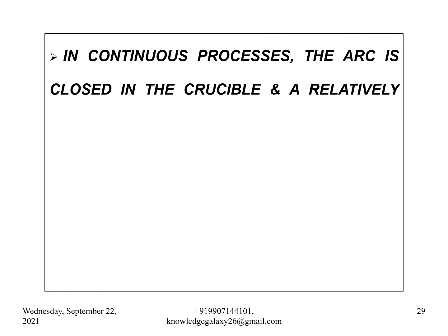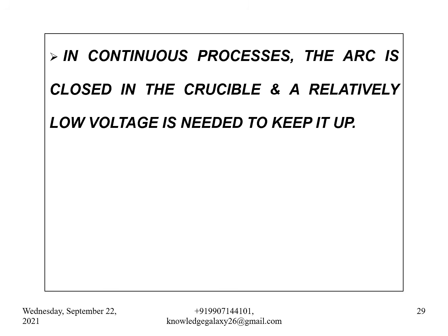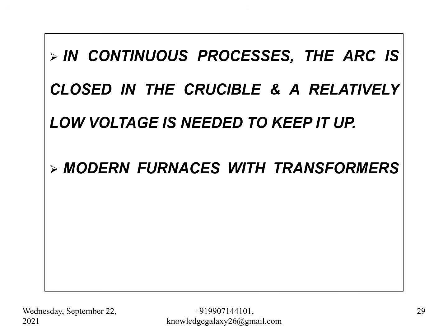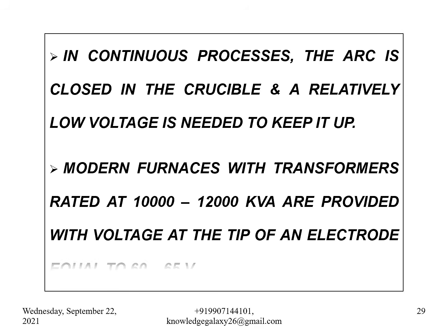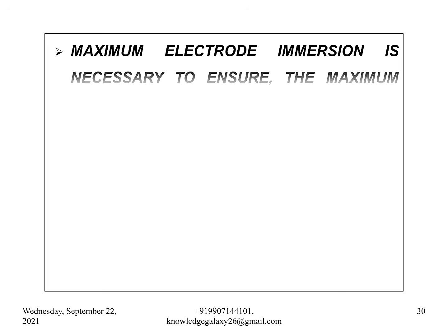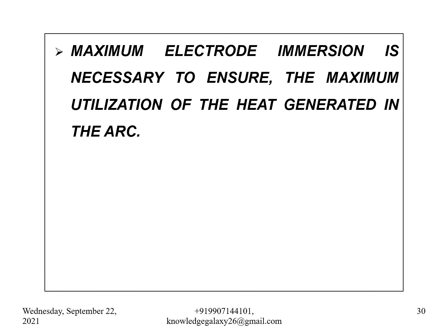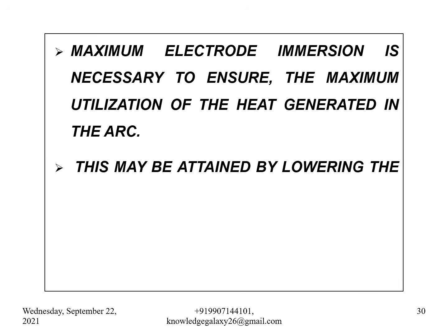In continuous processes, the arc is closed in the crucible and a relatively low voltage is needed to keep it up. Modern furnaces with transformers rated at 10,000 to 12,000 kVA are provided with voltage at the tip of an electrode equal to 60 to 65 volts. Maximum electrode immersion is necessary to ensure the maximum utilization of the heat generated in the arc. This may be attained by lowering the secondary voltage.